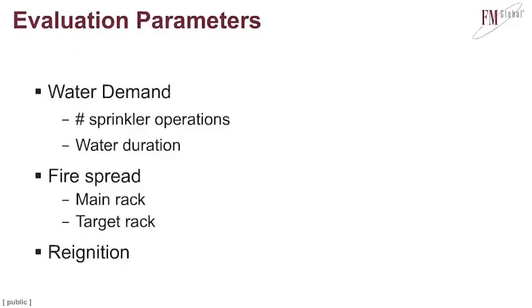The energy storage systems are kind of unique in that the fires can last much longer than ordinary combustibles. So we made some additional considerations to make sure that there's enough water for the entire duration of the event. Also looking at the fire spread, particularly does the fire stay within the main rack, or would it spread to a neighbor? And the last one, and this is a very well documented concern for lithium-ion batteries, is the potential for reignition.